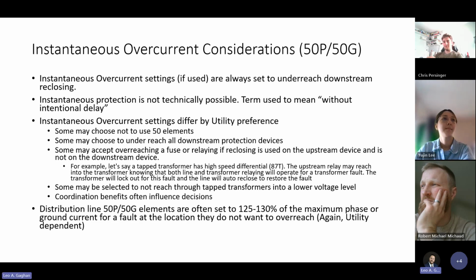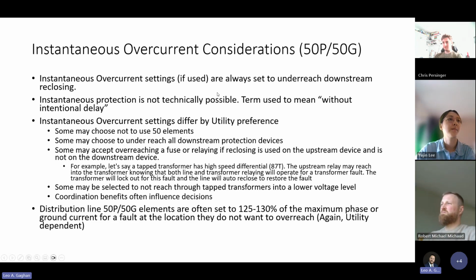But preferences for instantaneous elements tend to differ by utilities. They seem to always have their own standards. I think I kind of skimmed over this top note, but they're always set to underreach downstream reclosing. And that's just because we need to coordinate with that downstream reclosing. If we both open and we both reclose, it usually gets you into not a good situation. So some utilities may choose to not use instantaneous elements.